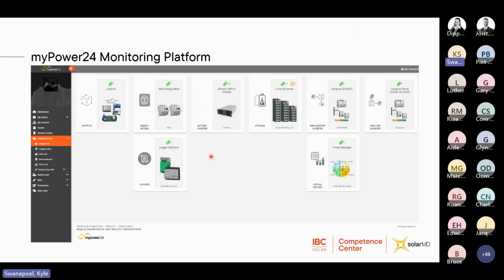Right. So just to go back to this one here, we have the dashboard, which I'll show you now, and then you also have charts. So there's a power chart as well as an energy chart. We're viewing my devices now. There is also events, so that you can go and view if there were any events within these devices. If it was a disconnect of a specific device, maybe there was a high cell voltage incident with the battery. Yeah, whatever it might be will be stored under the events. And then, Rian, the local data is stored indefinitely until the memory card is full. But I've seen loggers with 5 years of local data that can still log local data.